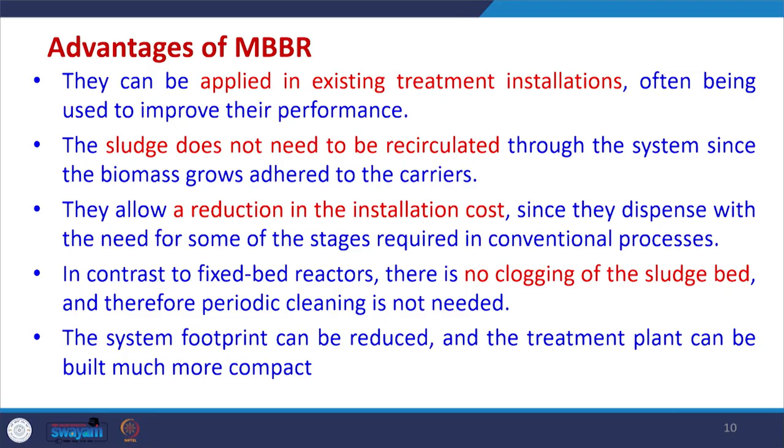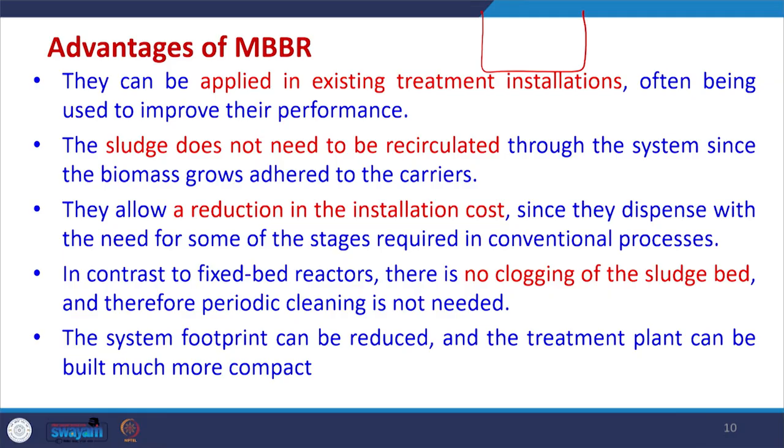Now, there are certainly some advantages of MBBR. They can be applied in the existing treatment installation. What does it mean? Suppose we have an activated sludge process. In place of the activated sludge process, we can use these carriers along with their biofilm. We can just put them inside the system and start using this MBBR system in place of the activated sludge system. The only thing is that we have to use more air so that this system moves all inside the reactor in a floating mode. So, we can use the existing treatment installation for MBBR.